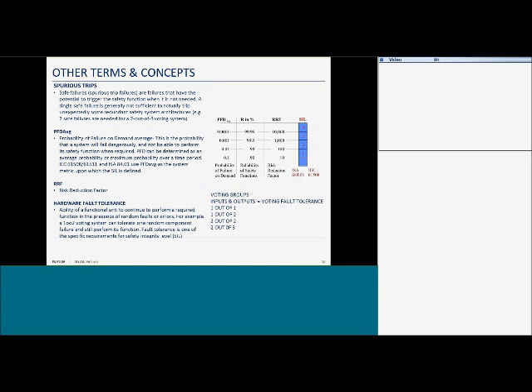Some other terms, spurious trips. This is a term that comes straight out of IEC 61511. This is the bane, really, of existence for safety shutdown systems. A spurious trip is basically a trip of the system that had nothing to do with a hazardous event, but had something to do with some sort of failure or fault within the system. These are unfortunately very common, something our customers battle on a regular basis, something they want to do everything possible to eliminate, and it's a great opportunity for us to get involved and offer our assistance. And so we're going to come back to spurious trips a little later in the presentation and focus on that.